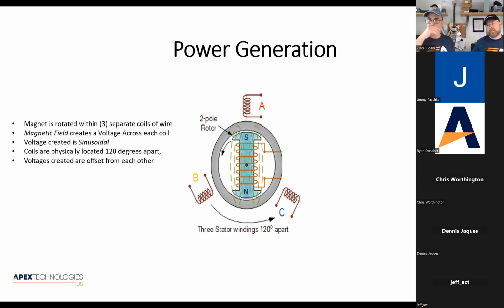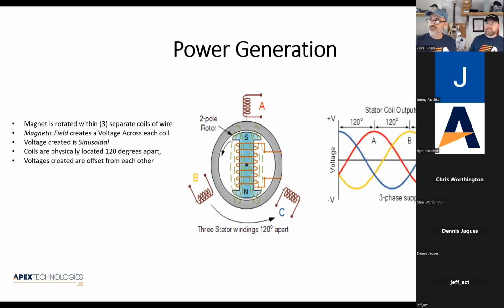In other words, instead of putting electrical power into a motor to cause a rotation, with a generator you rotate a magnet with windings wrapped around it, and that causes an electrical current in the wire. The way they build these generators is they have 3 sets of windings spaced equally apart, 120 degrees apart rotationally. And why that is important is because it creates 3 sine waves simultaneously. They could very easily have put 4 windings on there at 90 degrees apart, and we would have called that 4-phase power instead of 3-phase power. But this is where 3-phase power comes from: those generators have 3 windings creating these sine waves. You can see the sine waves don't all line up. They're not right on top of each other. But we'll talk a little more about 3-phase as we go along.